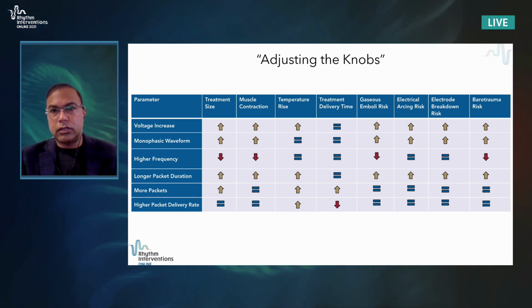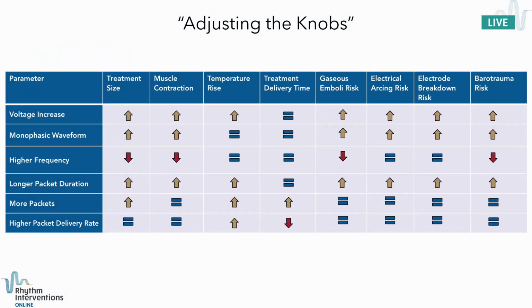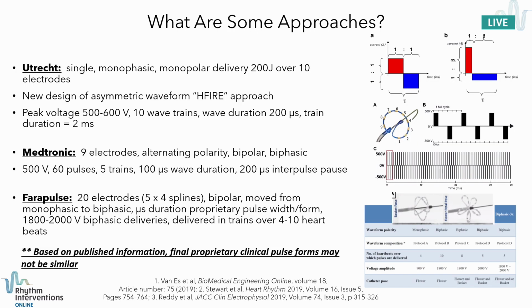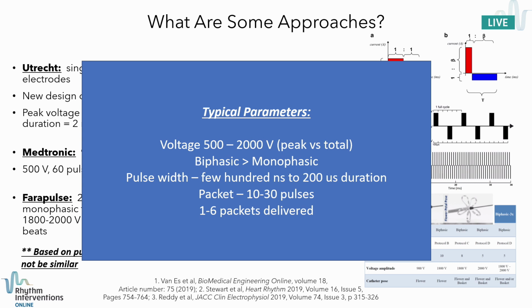Now, there are many ways that you could adjust pulse fields in order to get the optimal pulse field ablation. And I'm not going to go into each of these different buttons or knobs that you can adjust. However, this is a science in and of itself and very, very fascinating, quite frankly. In general, there are many approaches being used out there, but the typical parameters for most PFA systems are a voltage of about 500 to 2000 volts, biphasic more so than monophasic. The pulse width is generally a few hundred nanoseconds to about 200 microseconds on the outside, with 10 to 30 pulses per packet, and generally 1 to 6 packets being delivered.